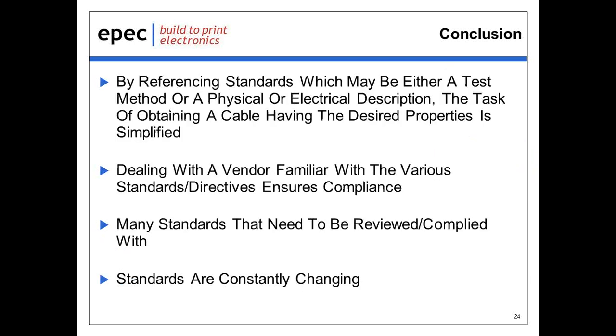In conclusion, referencing standards that need to be met when ordering an assembly simplifies the entire process. The producer of an assembly, such as ourselves, can associate with the standard, which will specify in most cases exactly what raw materials need to be used, the electrical characteristics the assembly needs to be tested to and meet or exceed, as well as other characteristics such as chemical resistance or sterilization. Dealing with a supplier familiar with those standards and directives will ensure an assembly is produced that complies with the standards you're most interested in.